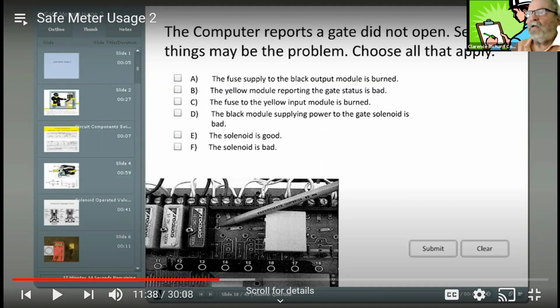Okay, computer reports the gate did not open. The fuse that supplies the black module is burned. That could be true. How about the yellow module reporting the gate status is bad? I would say that could be true, because your computer wouldn't know if that opened or closed, and so therefore it reports that. So I would say that's true too. Not bad, Jeff. How about C? The fuse to the yellow input module is burned. True, because it didn't report going back. The fuse would have kept that from doing it.